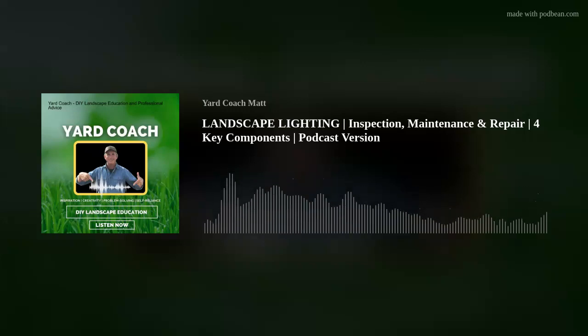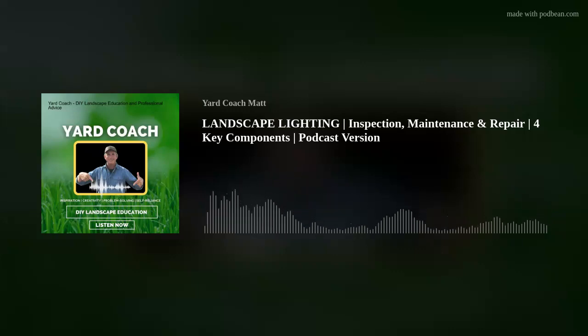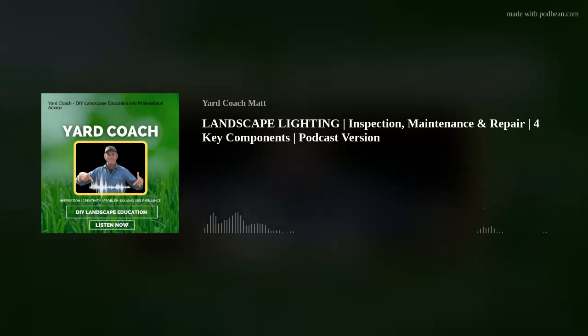Now, if they're not on, we have to determine why. Obviously, a process of elimination enters into this. Is it the bulb? Is it the fixture? Is it the cabling, etc.? We don't know, so you have to start somewhere. If it's only one bulb on one cable, chances are it's going to be the bulb. Probably not if you have multiple bulbs out on the same line. Then you've got either a voltage spike that came from the transformer, you've got really old bulbs, no maintenance has happened for quite a while, or something else. You've got something in the cabling world that might need to be addressed.